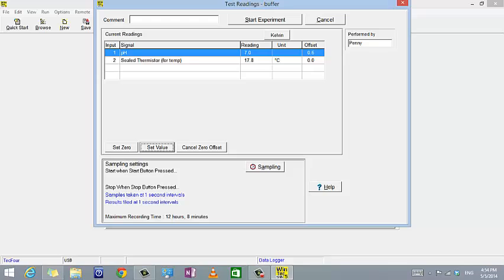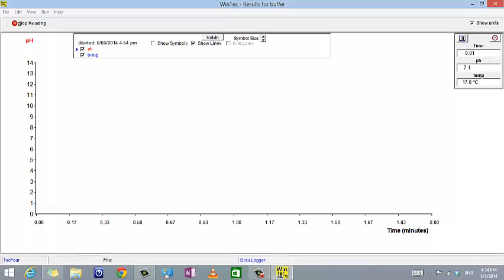So on your pH amplifier, you want to adjust that so that your temperature reads okay. And that gives you a little bit of an offset on that. There's also a bit of asymmetry in there, which you can adjust for the pH as well. You can do that before you change your zero offset if you want. And that's the blue button on the pH amplifier. Once you've set that, you just start your experiment and it should start running. In the corner up on the right, you'll see pH and temperature.